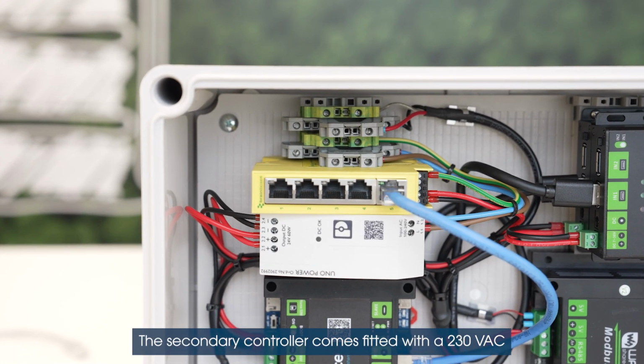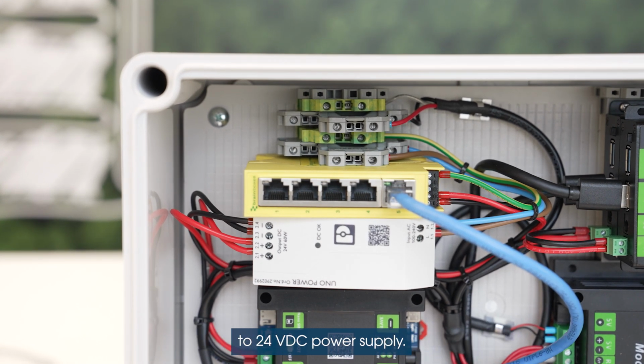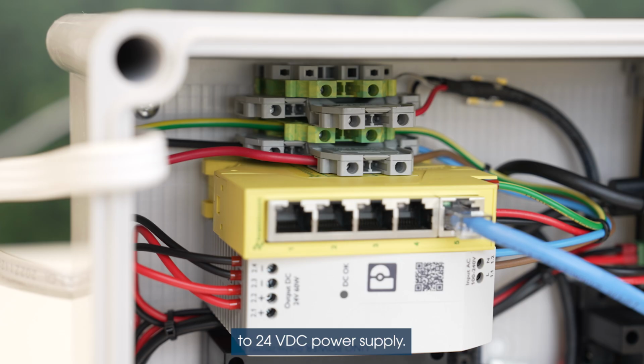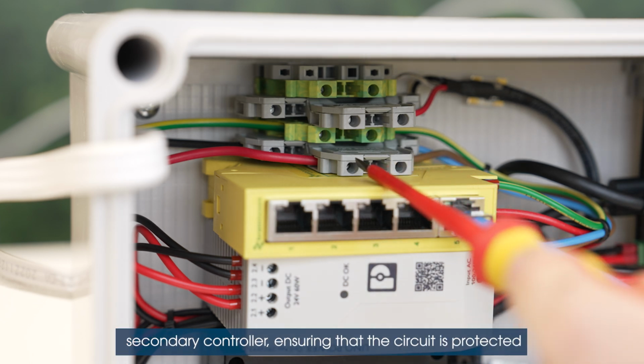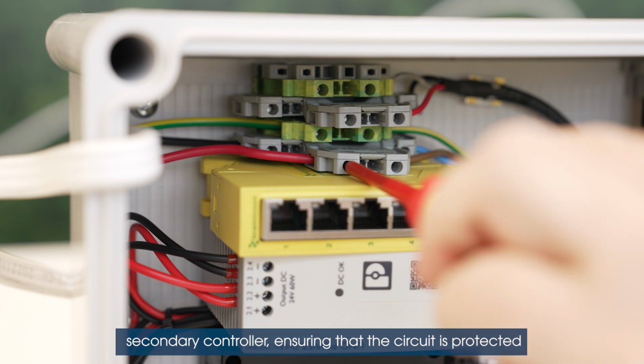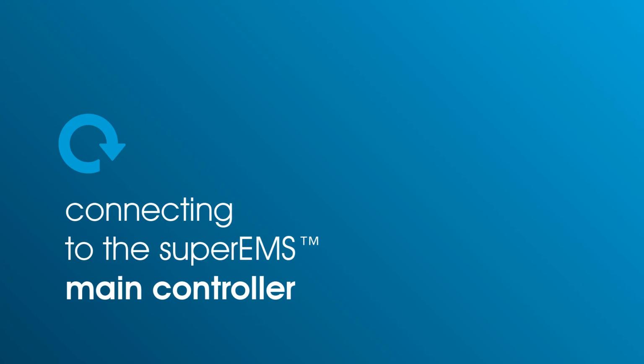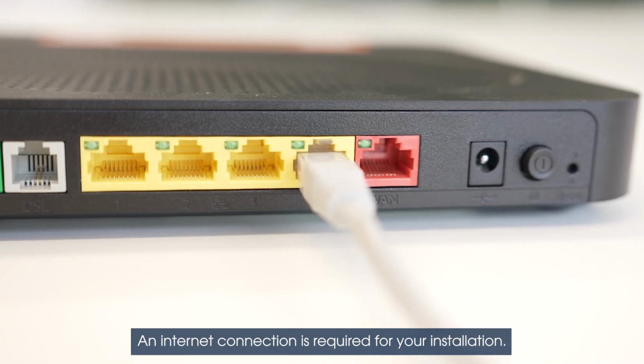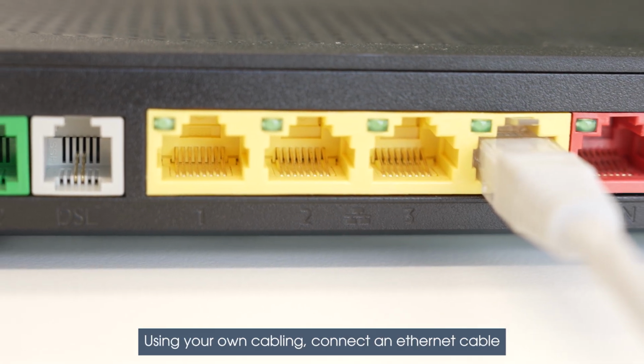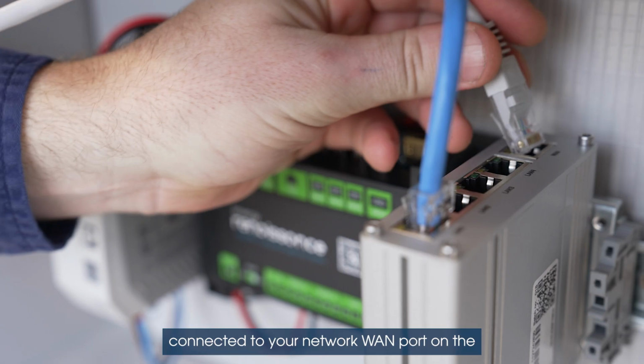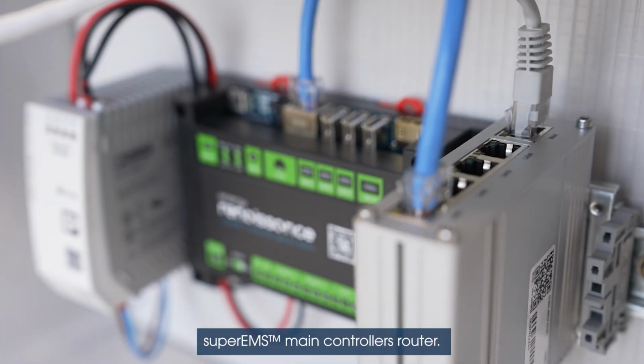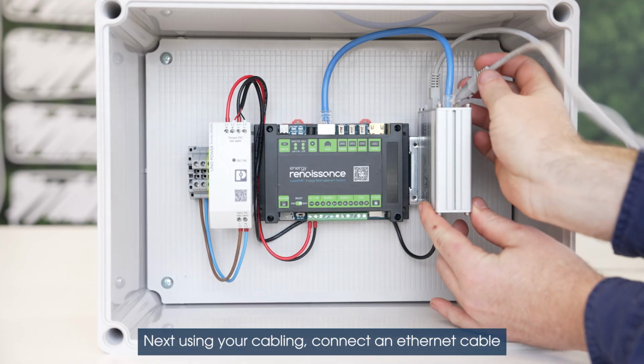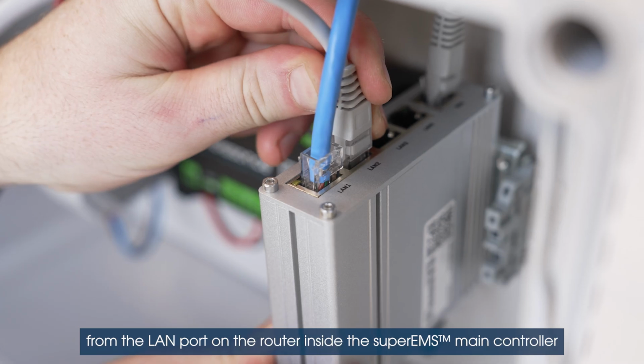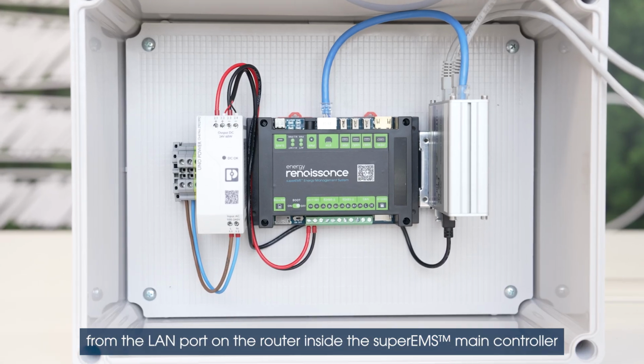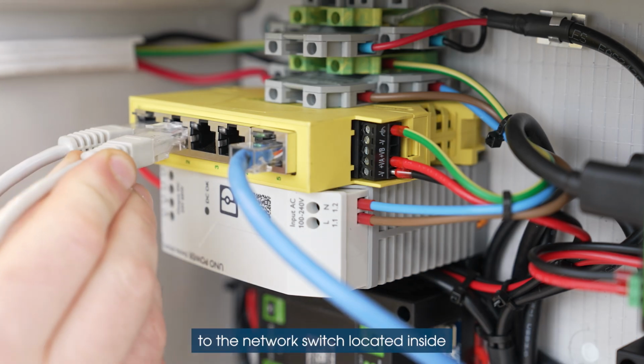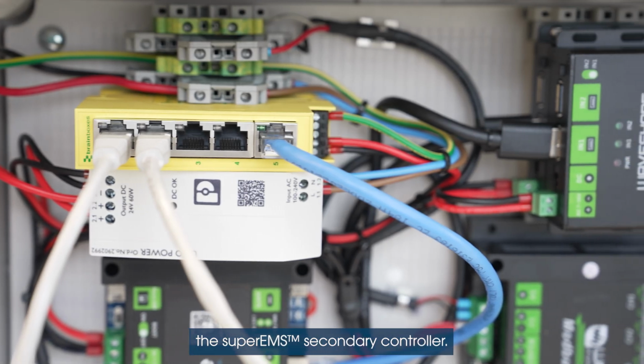The secondary controller comes fitted with a 230 volt AC to 24 volt DC power supply. Using your own cabling, connect the power to the secondary controller, ensuring that the circuit is protected with a suitable circuit breaker. An internet connection is required for your installation. Using your own cabling, connect an Ethernet cable connected to your network WAN port on the superEMS main controller's router. Next, using your cabling, connect an Ethernet cable from the LAN port on the router inside the superEMS main controller to the network switch located inside the superEMS secondary controller.